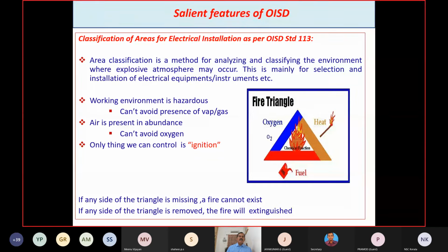So actually, we cannot rule out the presence of an explosive atmosphere where there is processing, handling, and storing of petroleum. Because if you take the fire triangle, it's a basic fundamental which tells why fire burns, and also suggests the way for fire prevention and fire extinguishment. As per this, the working environment is hazardous. We cannot rule it out. That is our business. So we cannot avoid an explosive atmosphere. Similarly, air is present in abundance and oxygen will be 21%. We have to breathe, and that also we cannot avoid. So the only thing we can control is the ignition source.